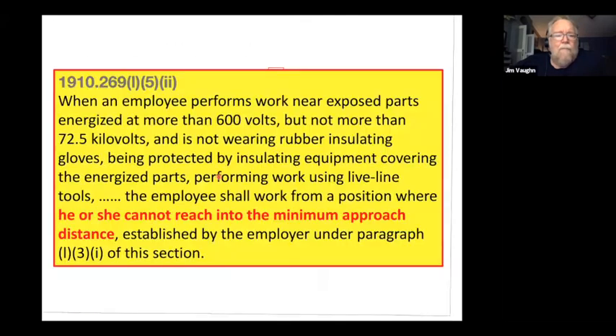Let me move along here because I'm going to run out of time, and I don't want to get too far away. But look at this rule from here, L52, related to what we just looked at. When an employee performs work near energized parts at more than 600 volts, but not more than 72, and is not wearing rubber insulating gloves, being protected by insulating equipment covering energized parts, or performing work using live line tools, the employee shall work from a position where he or she cannot reach into the minimum approach distance established by the employer. And so this is what that would look like.